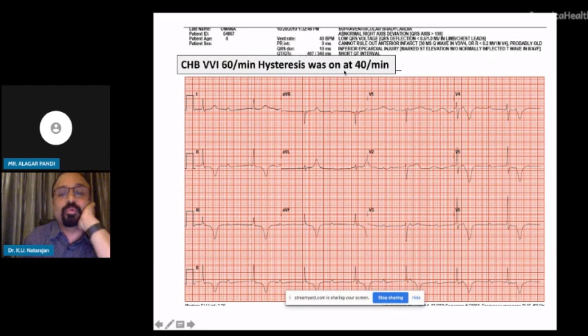That is the concept. So here, the pacemaker was programmed at 60 VVI, but hysteresis was programmed at 40, meaning when the rate comes to 40 or less than 40, the pacemaker will function at 60. To the contrary, if the patient has a rate of 50, the pacemaker will not work. This is a normal function. So here there is a ventricular rhythm at 40 per minute. The pacemaker is not functioning because hysteresis is on. So this is not a defective pacemaker system. It is something to do with the way we have programmed the pacemaker.